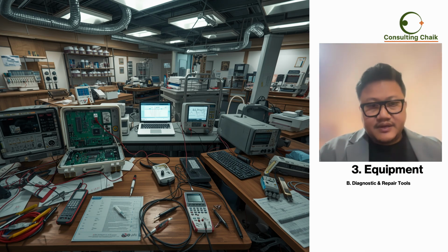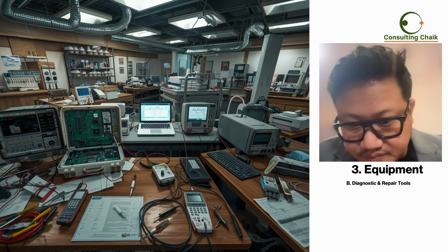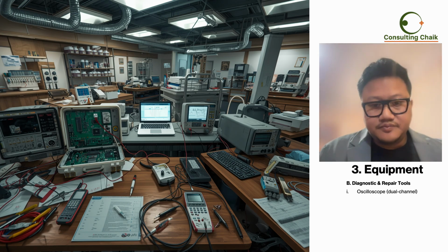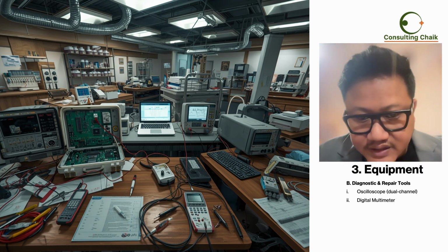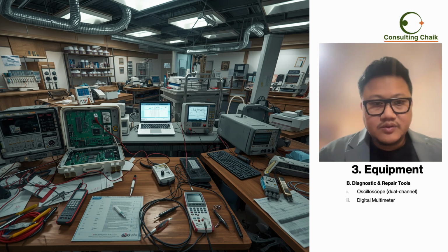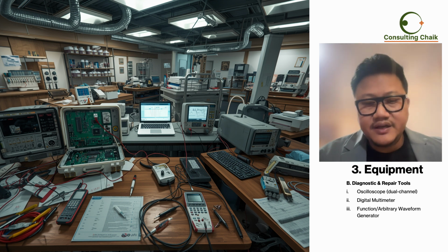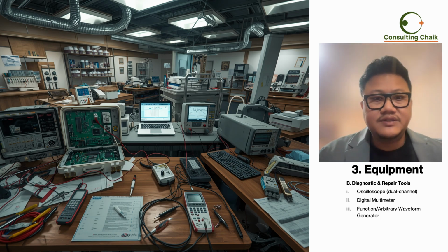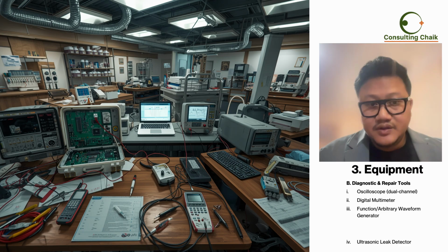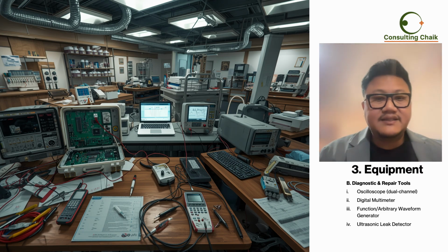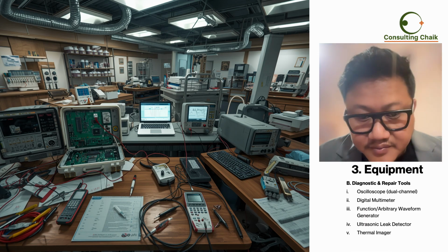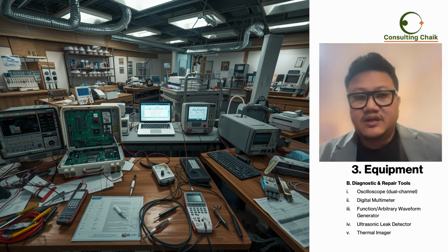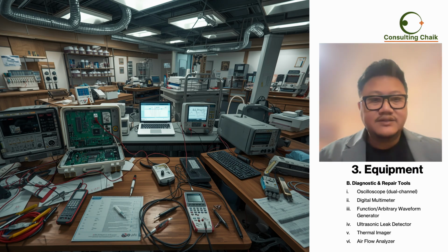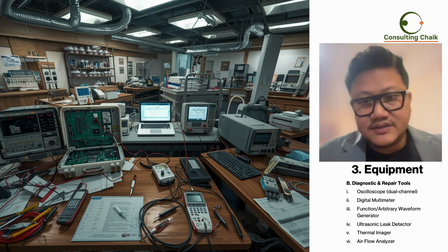Then the second type, diagnostic and repair tools. Like your oscilloscope, which is dual channel, your digital multimeter, so it's voltage, resistance, continuity testing, all that can be done through this. Then you have your function arbitrary waveform generator, which does signal injection for device calibration. You have your ultrasonic leak detector, which detects gas leaks. You have your thermal imager, which identifies overheating components. You have airflow analyzer, which is used for ventilator respiratory device flow validation.